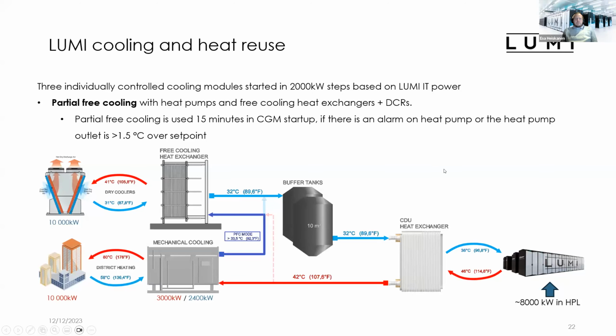Then we have this partial free cooling with heat pumps, free cooling heat exchangers and dry coolers, and this is done in series. So first the heat pump is doing the cooling, and then the free cooling heat exchanger is taking the rest of the heat out from the liquid to maintain 32 Celsius degrees to the Lumi.